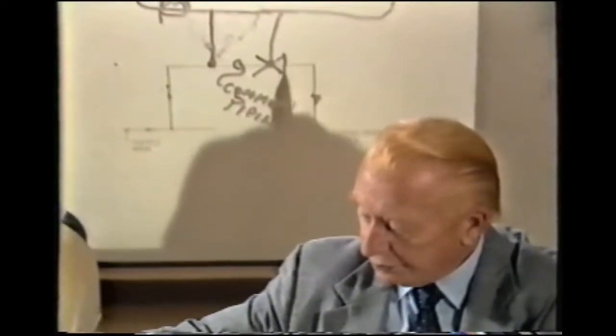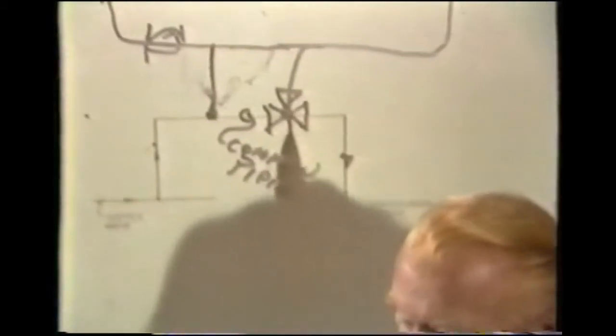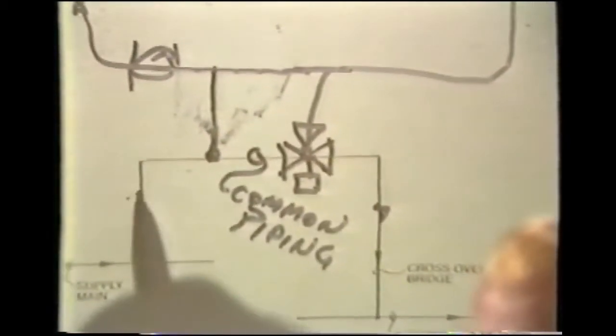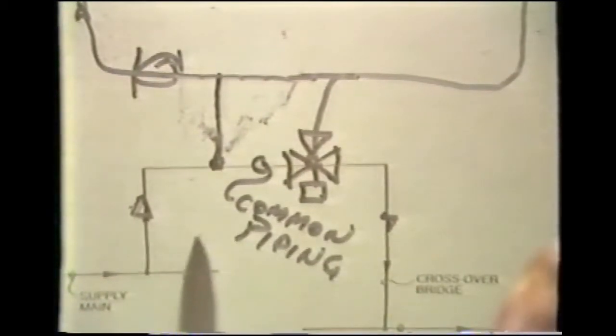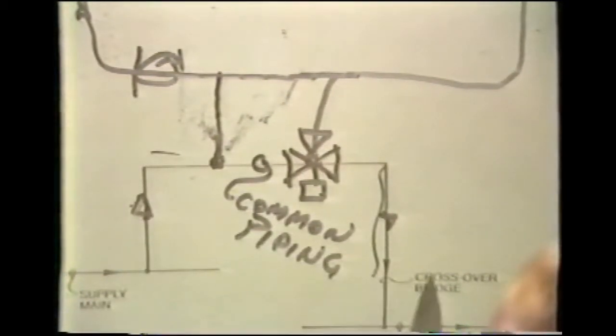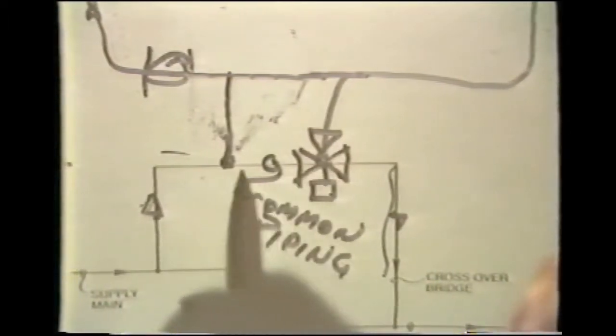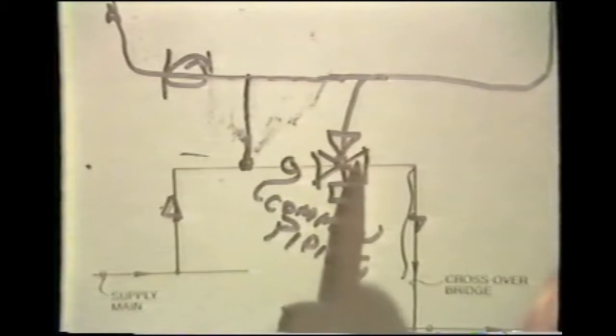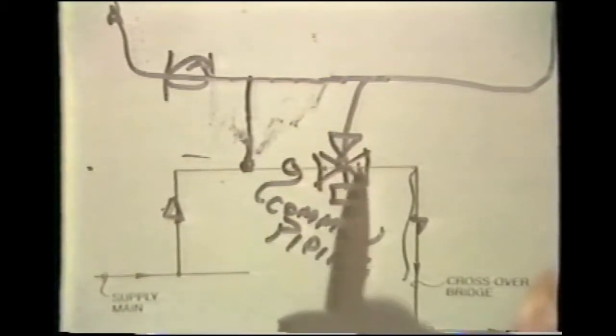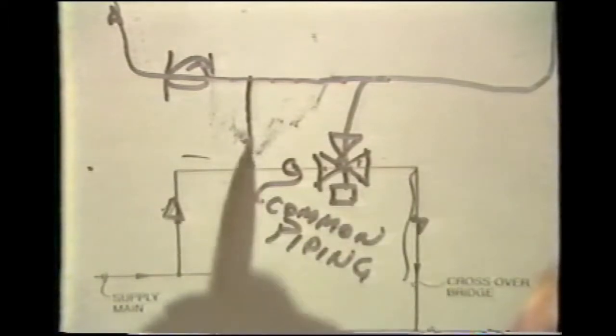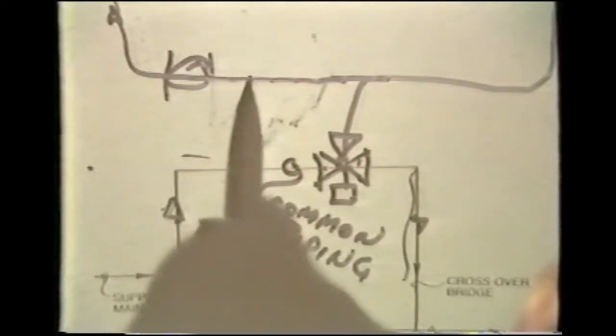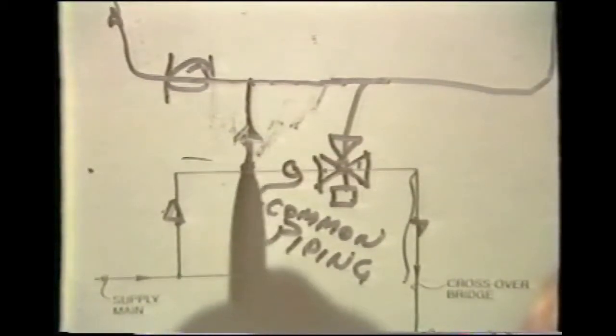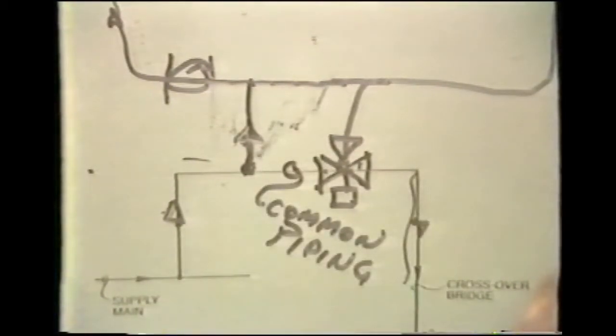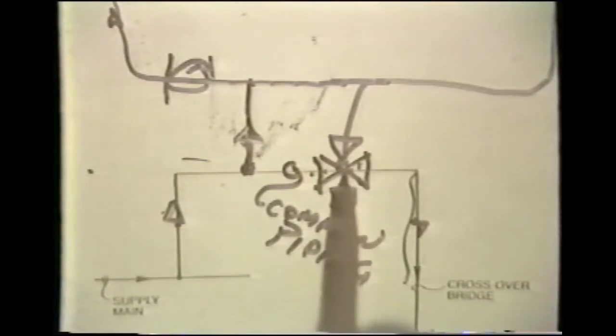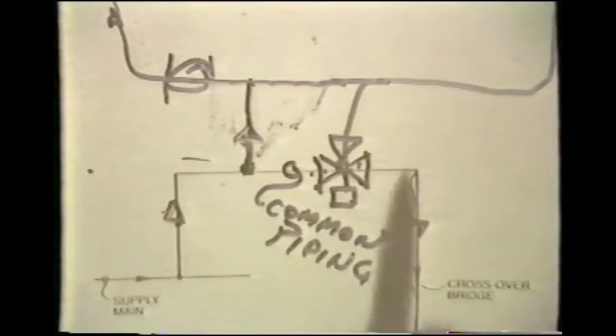And the simple change was this. We placed the mix valve in the crossover bridge, sizing that mix valve to the size necessary for the proper flow distribution into the crossover bridge itself. This meant the valve was smaller. Because it's smaller, and because it was sized to the flow rate it was actually controlling, which is the flow rate in the bleed line from the crossover bridge into the secondary circuit, we then had better control at a lower cost.